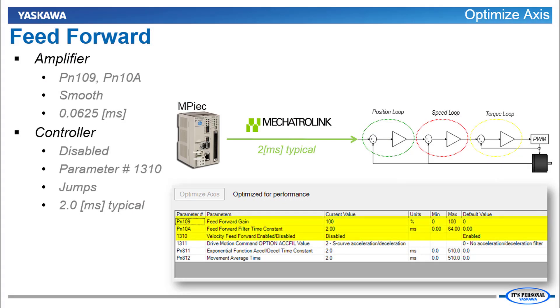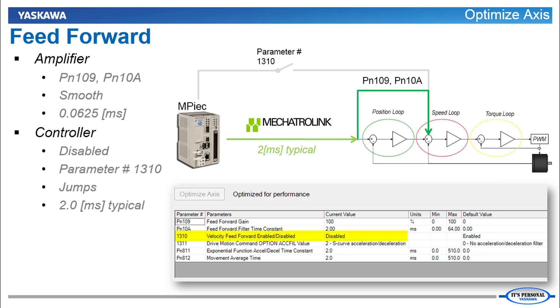The top three parameters in this list all relate to velocity feedforward. Feedforward takes the speed of the position command as an input to the speed loop and results in reduced position error. The amplifier internal feedforward gain and filter result in a smooth response because they operate at the internal update rate of the amplifier. The controller feedforward operates at the Mechatrolink cycle, typically around 2ms.